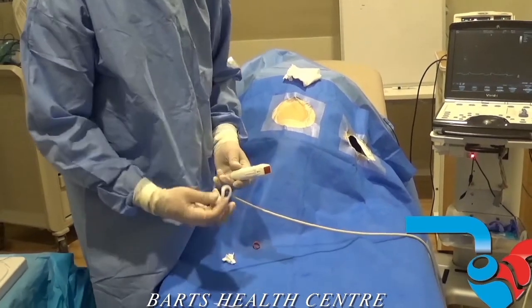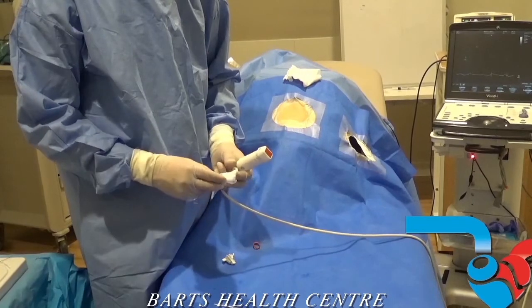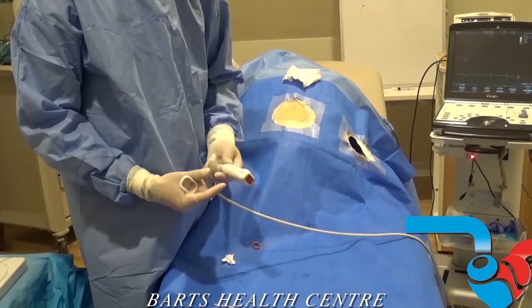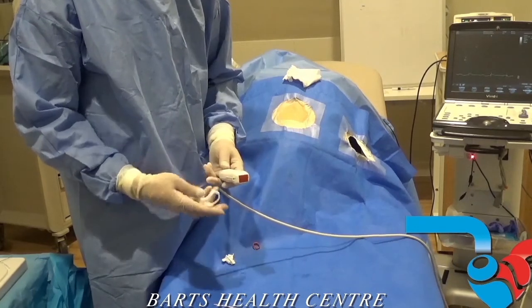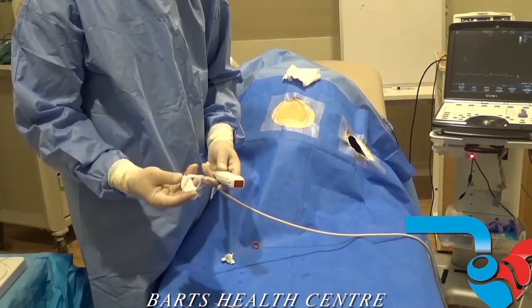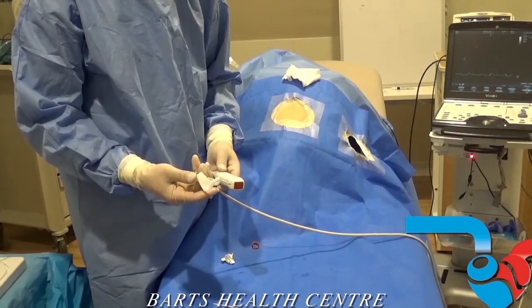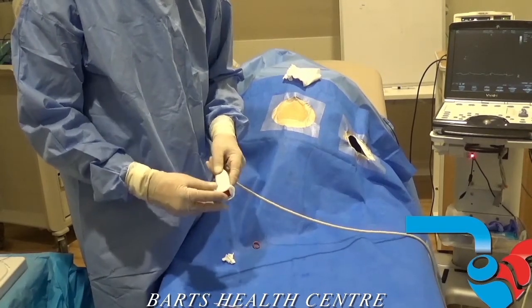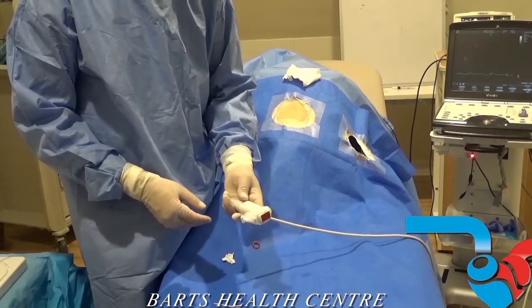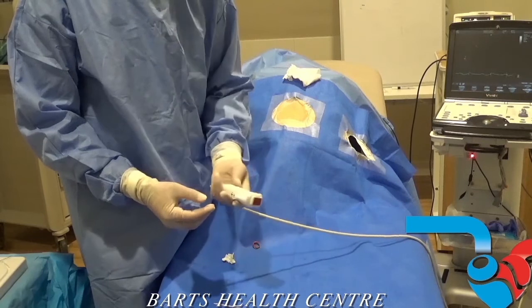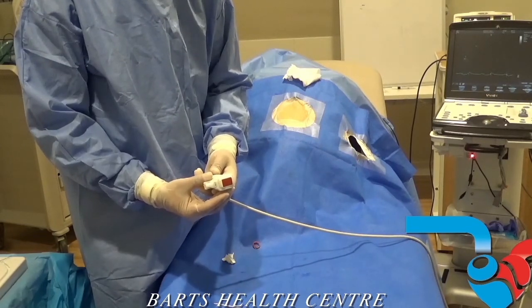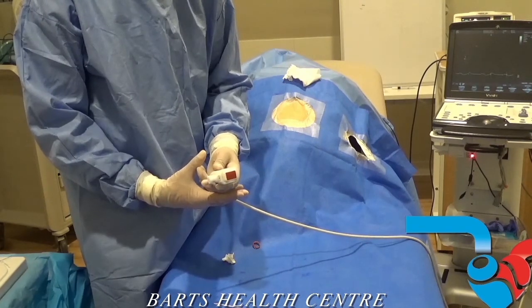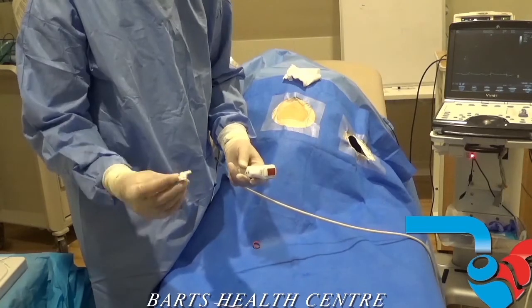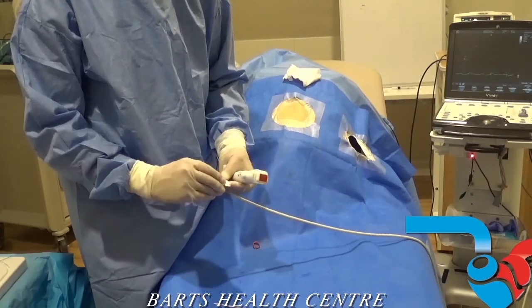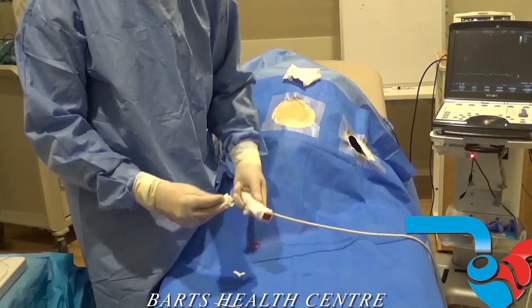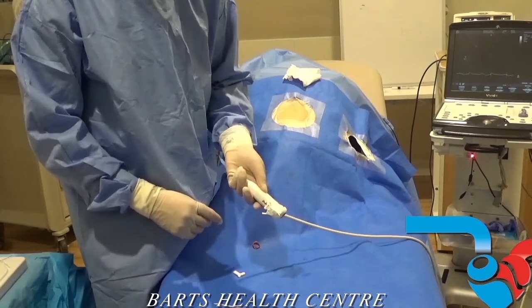So there are ways around this, and these are needle guides which are very familiar to interventional radiologists. Each ultrasound probe that's available, whether it's a linear probe or an echo probe, has specific brackets that are made by different companies. This is made by an American company, and it's designed to just clip on to that particular probe. This is the non-disposable, non-sterile portion, so we put this on first, and then we put a sterile sheath on this.